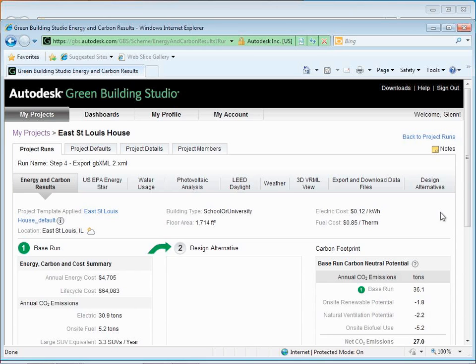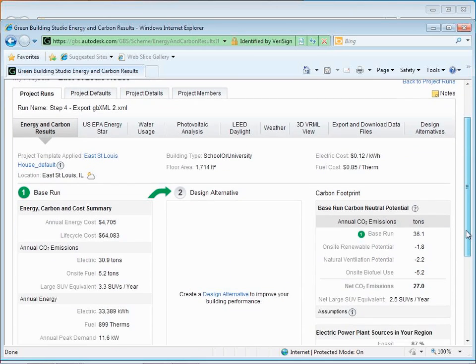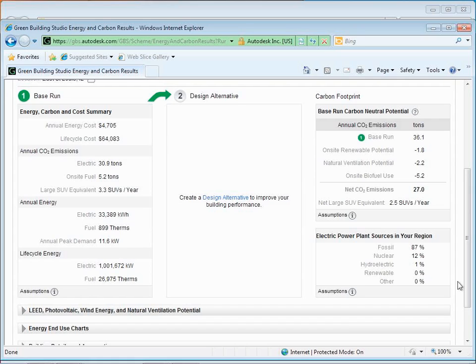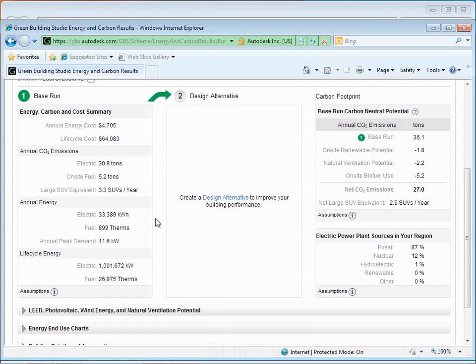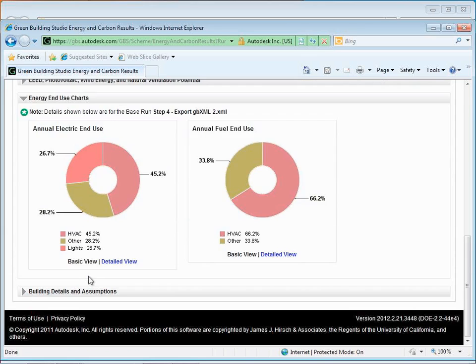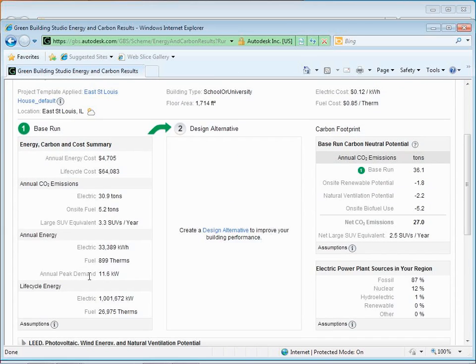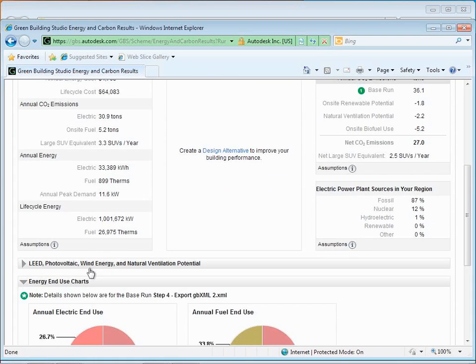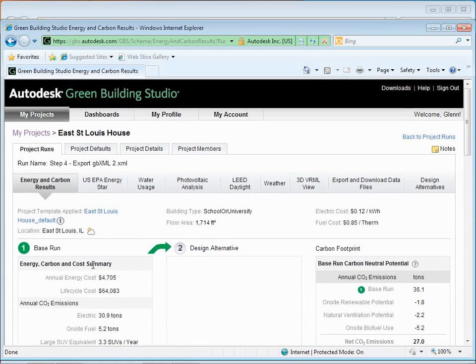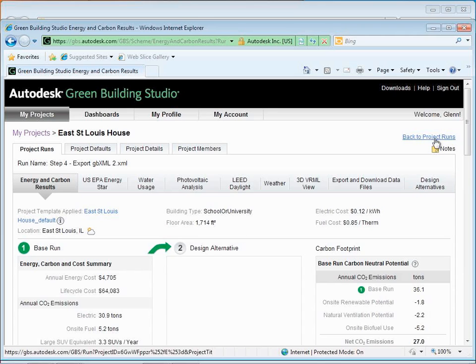So the report has a lot of different pieces. There's energy and carbon results - that's the overall notion of really how much energy we're using, both annually as well as across the lifetime. The difference is the life cycle cost is really 30 years discounted at I think 6%. It's telling us the annual CO2 emissions based on the fuel and electric use, telling us the actual fuel and electric use. And somewhere in here is actually the energy use intensity.